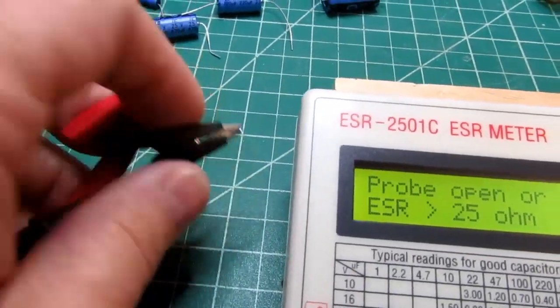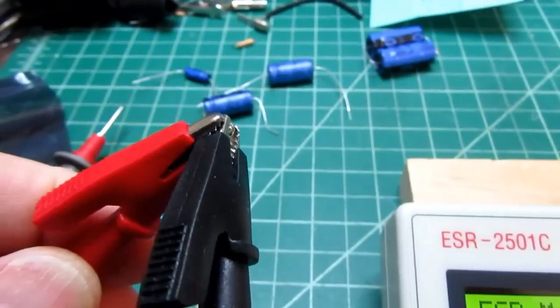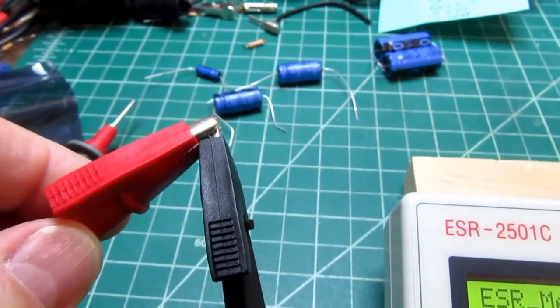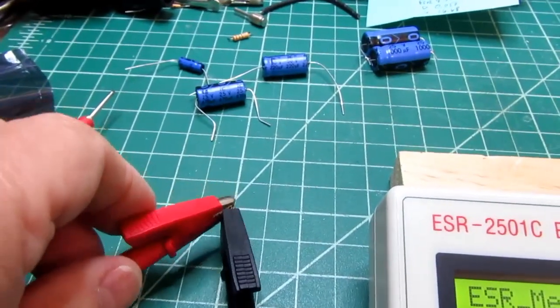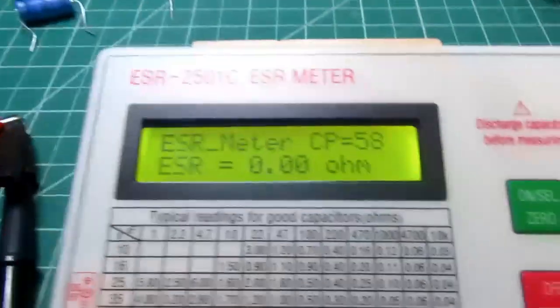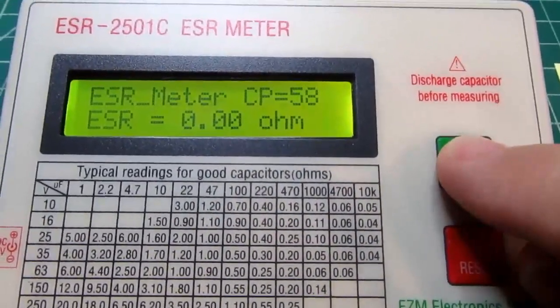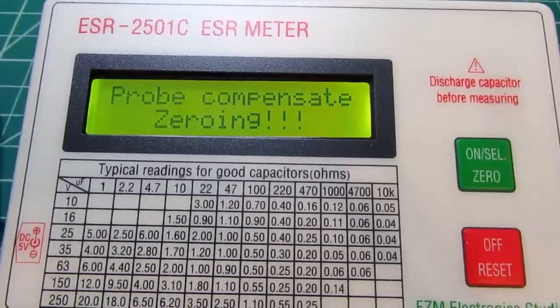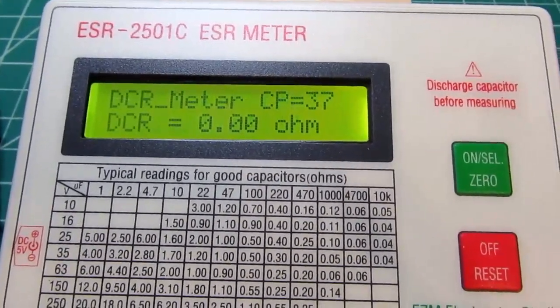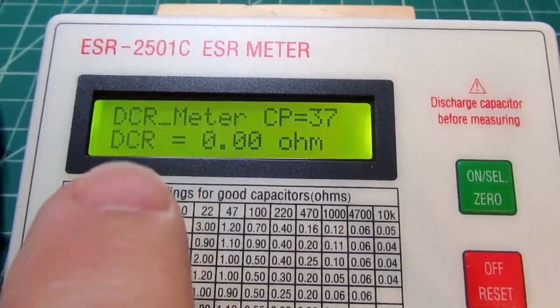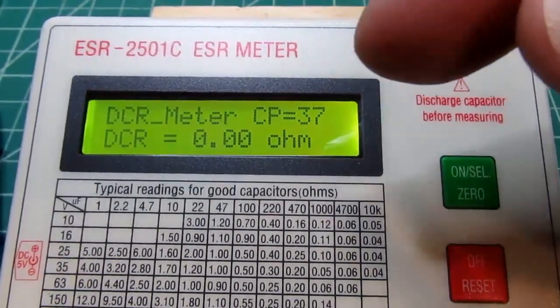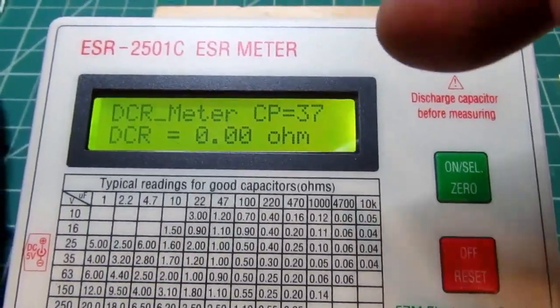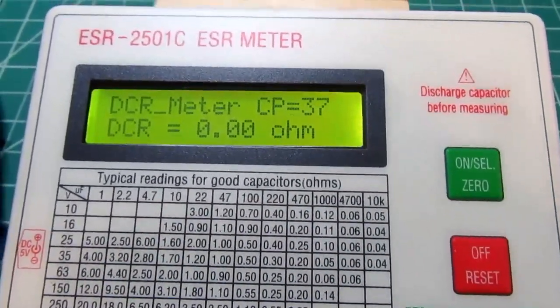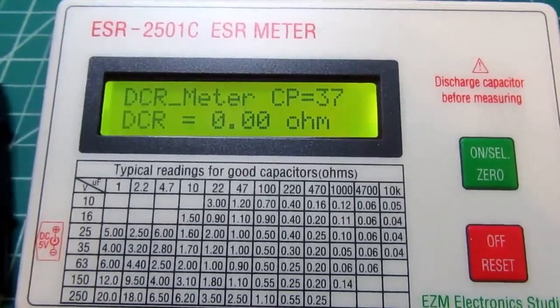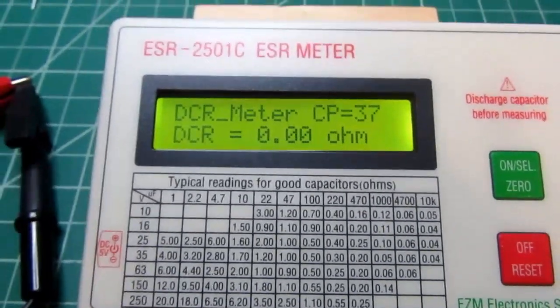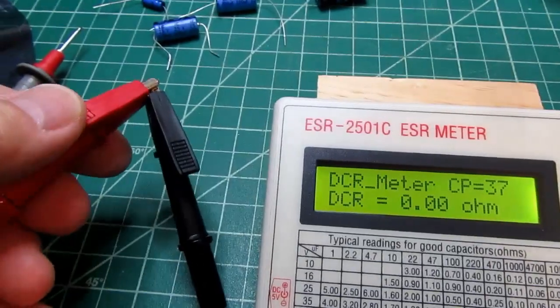So I'm just going to clip these together like this. You could also hold them together, but since I'm doing this one-handed, I get better results with them clipped together. I'll push the button to go to DCR mode, and it does a zeroing. Now it shows that it's in DCR mode, and the probe compensation is still about what it was for ESR, so the CP number should be similar. It's showing 0 ohms now, which is what you'd expect because it's shorted out.